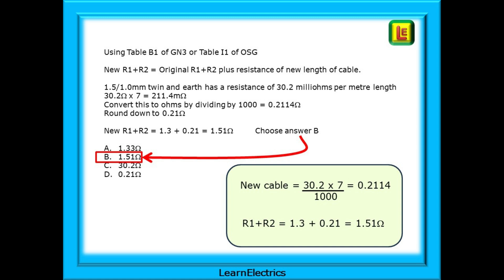We're not finished yet. That is just the new cable. Now we must add that to the resistance of the original. So the new R1 plus R2 is 1.3 ohms plus 0.21 ohms, making 1.51 ohms in total. And we should choose answer B.